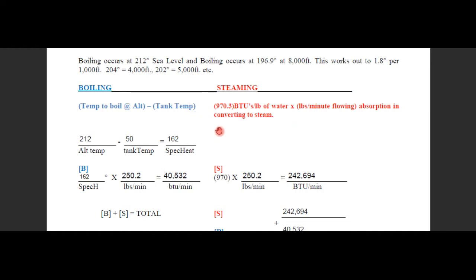You're dealing with two different situations of heat capacity going on simultaneously. Think of latent as happening later on. It's attached to the BTU, but it doesn't happen until a certain phase in the heat absorption process. You've got to get the water from its initial temperature up to boiling, and then you're able to take advantage of the water's greatest heat absorption capacity and put out fires once you get into the conversion to steam. If you see steam happening, you're taking the greatest amount of absorption capacity that you can out of your nozzle. Look for part 2, and we'll see you on the next one.